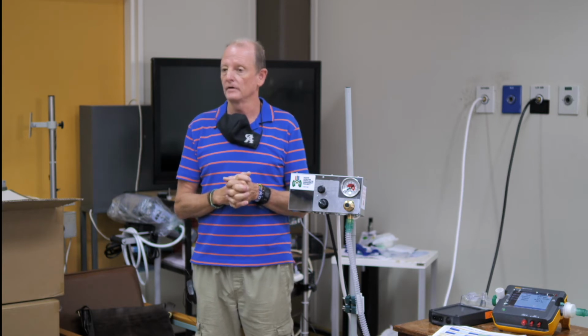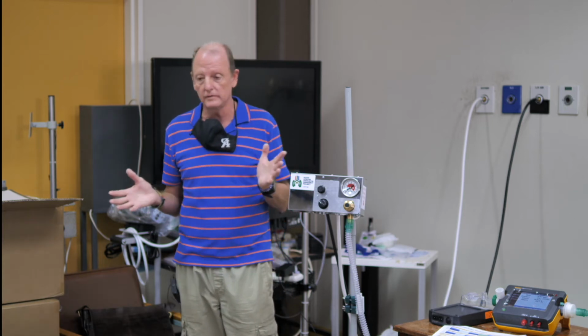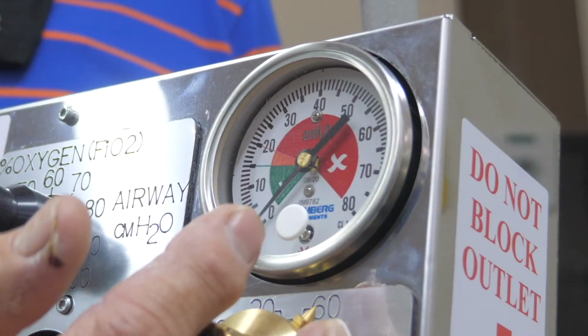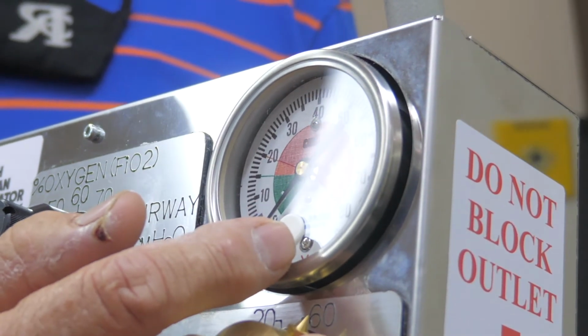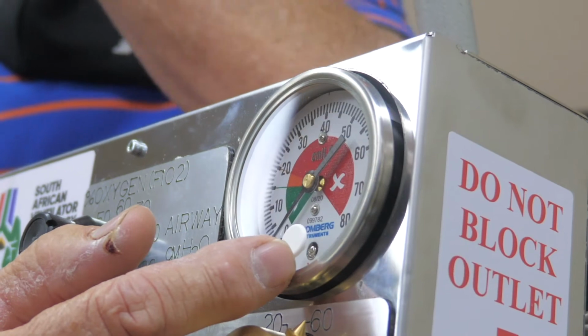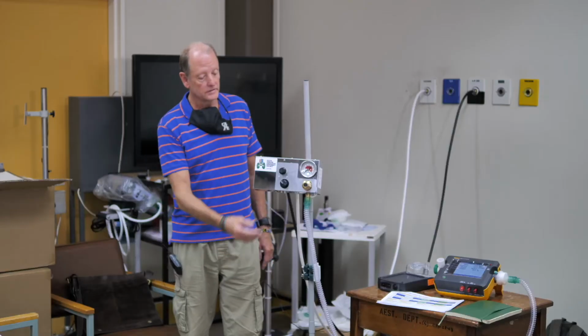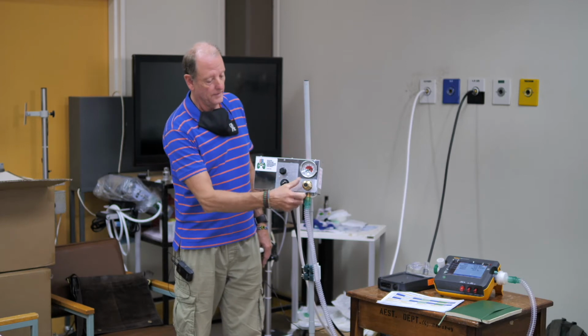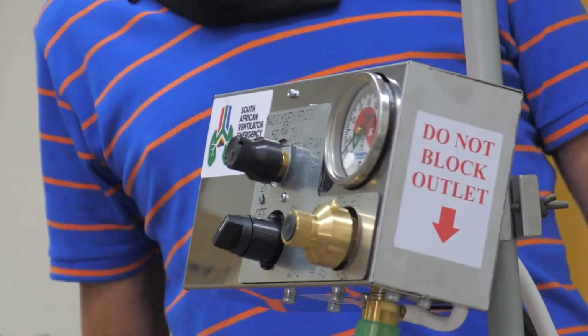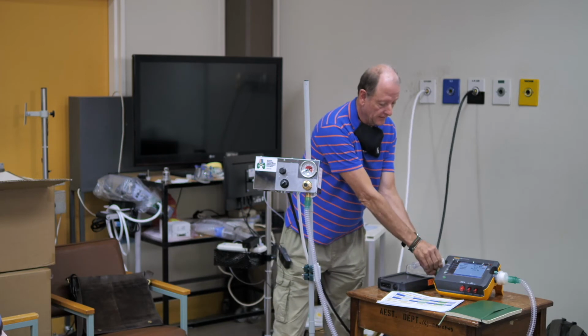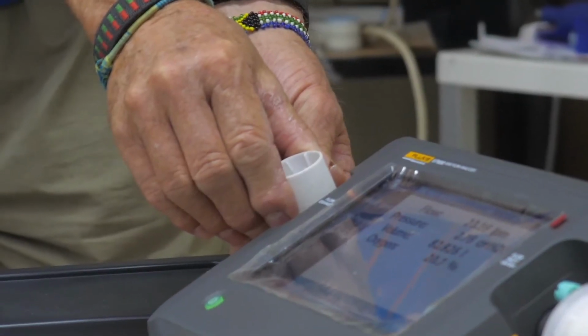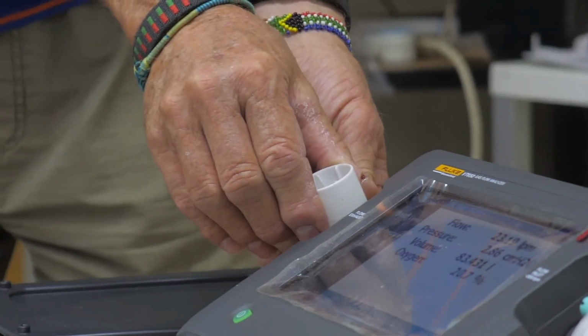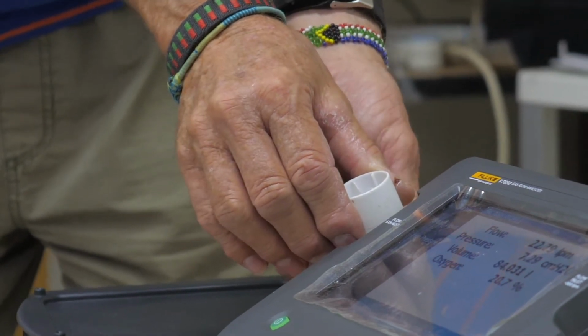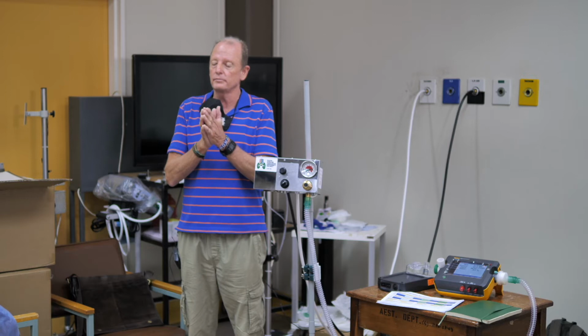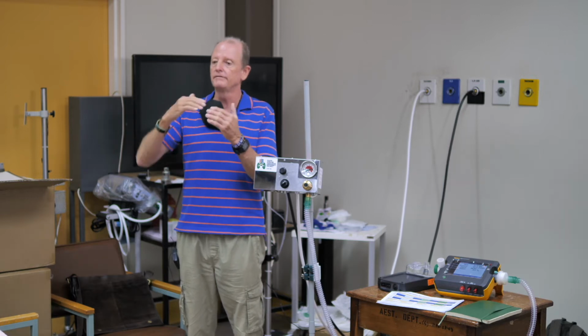So level 1, no tools allowed, no tools you need at all. You might need a screwdriver where you can adjust the gauge if the gauge is reading out slightly. You now want to just check the gauge as well, all right? So you'll switch it on, we'll go down to 20 liters a minute, and use this valve here to adjust up to roughly 10 centimeters of water reading here. Just make sure that your gauge is reading roughly. Remember, the gauge is not a precision instrument. It's purely a visual display.